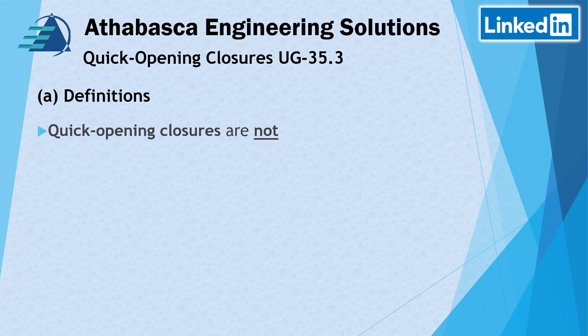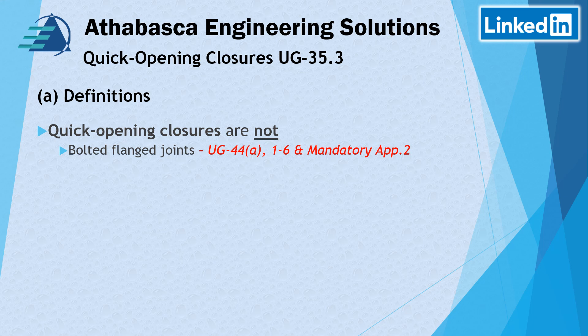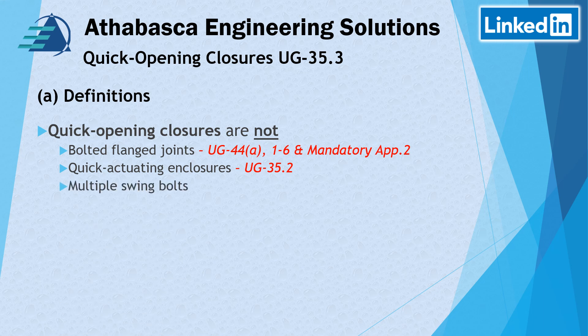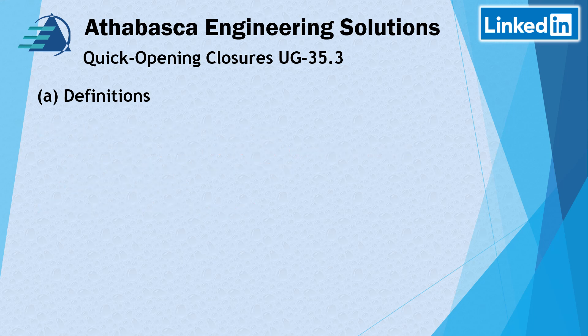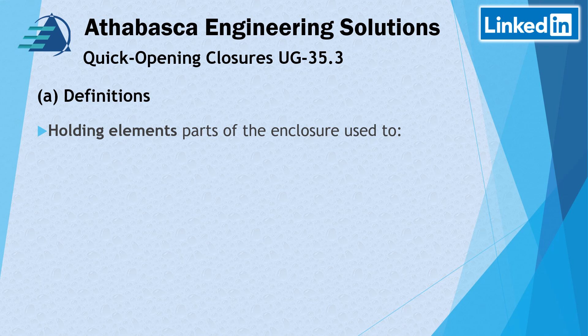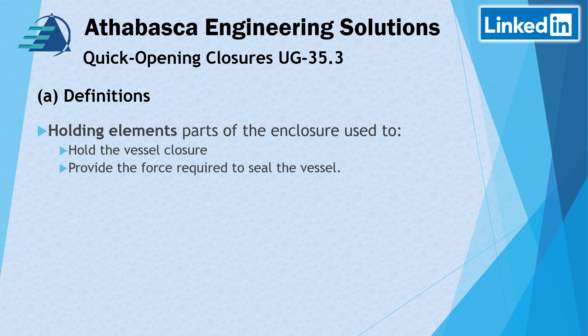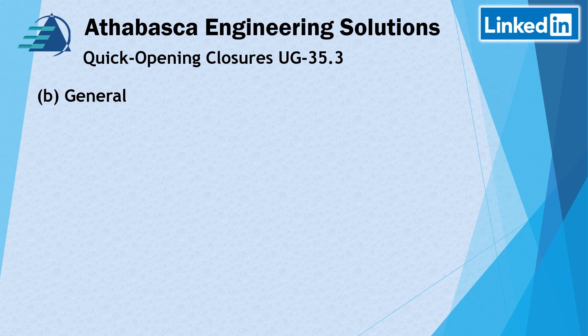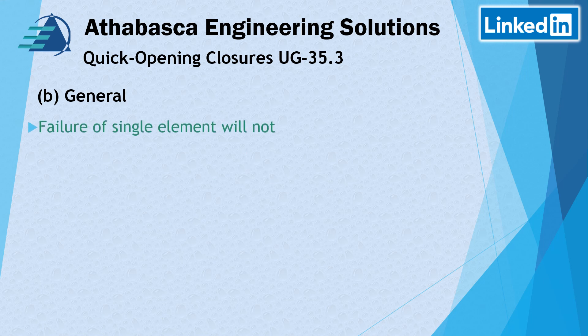A quick opening closure is not a bolted flange joint as described in UG-44(a), 1-6 and Mandatory Appendix 2. It is not a quick actuating closure as described in UG35.2. It is not a multiple swing bolt type of design, and it is exempt from Appendix 24.